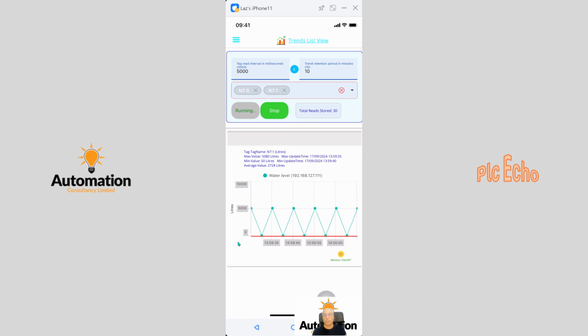You can see the total reads stored in the historical buffer is 30 tags. The reason for this is when you stop the trending, you can go back and analyze the value of your tags. If you want more tags to be stored in the historical buffer, just increase the trend retention period. If you want the trend to be faster, you have a tag read interval there in milliseconds. Change it, say, to 2000, which is 2 seconds. When you change it, make sure you press the Enter key to register.